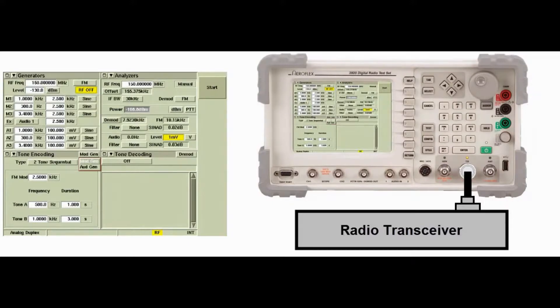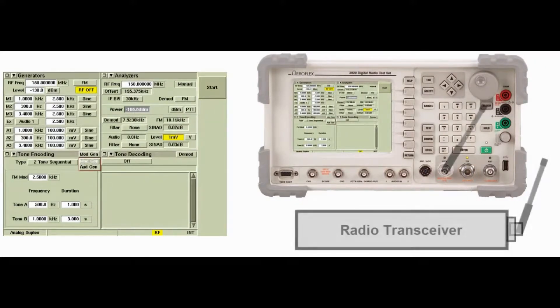The TR connector can be used to connect the signal directly to a transceiver. If the device under test is capable of transmitting high power signals and the GEN connector is selected as the instrument output, do not directly connect the GEN output to the transceiver. Instead, use an antenna.